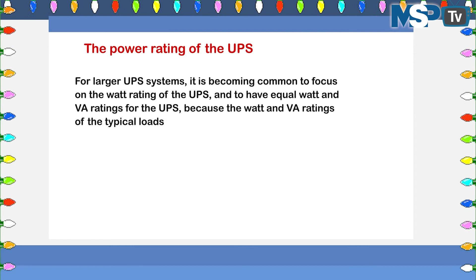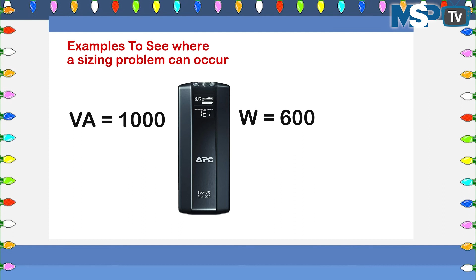Consider the case of a typical 1000 VA UPS. The user wants to power a 900 watt heater with the UPS. The heater has a watt rating of 900 watt and a VA rating of 900 VA, with a power factor of 1. Although the VA rating of the load is 900 VA, which is within the VA rating of the UPS, the UPS will probably not power this load. That is because the 900 watt rating of the load exceeds the watt rating of the UPS, which is most likely 60% of 1000 VA, or around 600 watt.